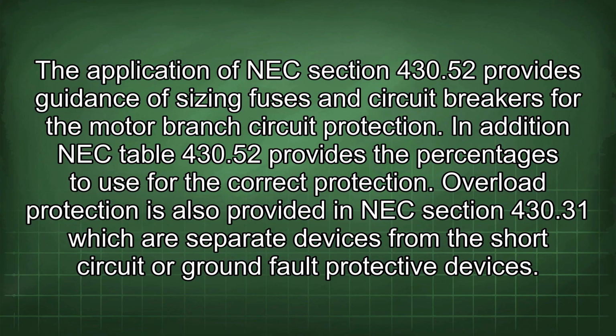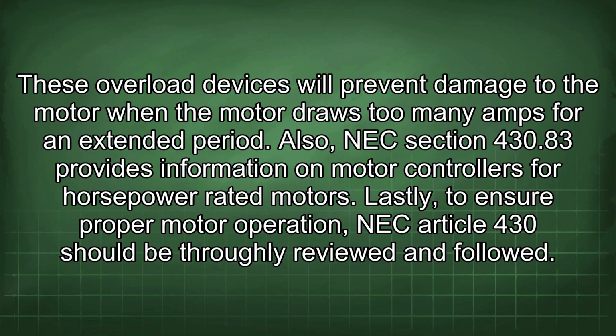Overload protection is also provided in NEC Section 430.31, which are separate devices from the short circuit or ground fault protective devices. These overload devices will prevent damage to the motor when the motor draws too many amps for an extended period. Also, NEC Section 430.83 provides information on motor controllers for horsepower-rated motors. Lastly, to ensure proper motor operation, NEC Article 430 should be thoroughly reviewed and followed.